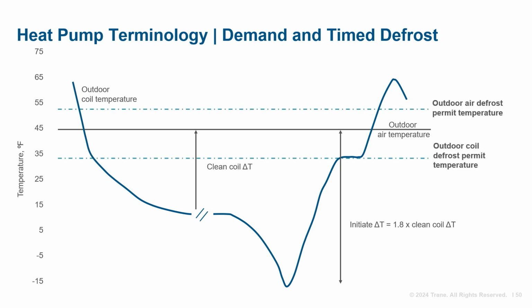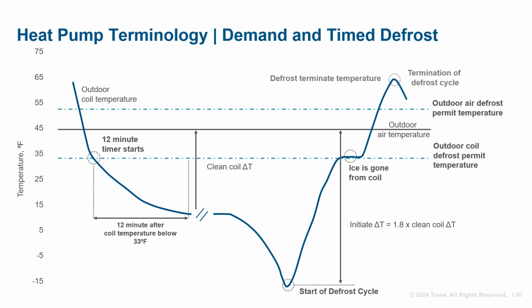The ambient temperature must be below 52 degrees Fahrenheit, and the outdoor coil must be below 33 degrees Fahrenheit. Once these conditions are met and the timed sequence has expired, the defrost sequence may be permitted. The unit will cycle the four-way valve and stop the outdoor fan. This process allows the heat of compression to melt any accumulated ice. Once the defrost conditions are met and the defrost termination temperature is satisfied, the heating sequence will resume.